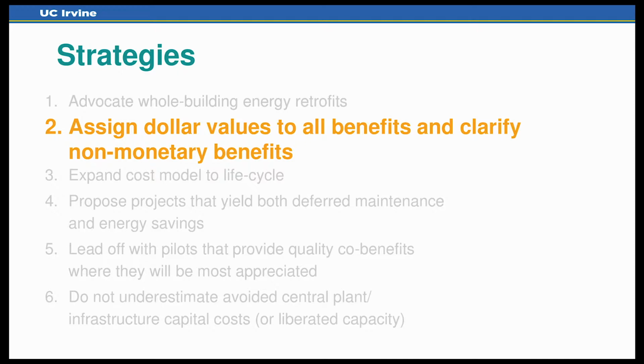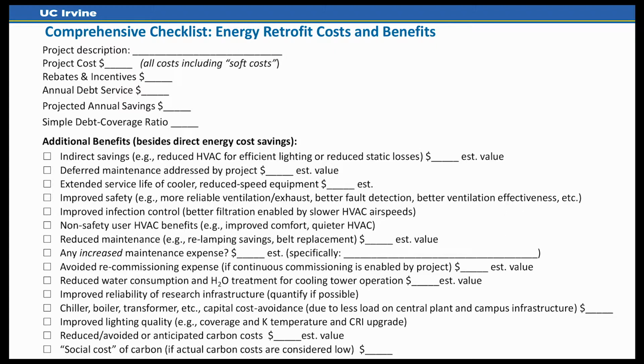So let's talk about examples. This is a typical energy retrofit project of about 10 years ago. So this isn't a whole building retrofit. This was actually before we started doing whole building retrofits. So this was a case of a building that had on the roof a whole bunch of individual exhaust fans, one for each fume hood actually. And they were belt driven. They were 1 and 2 horsepower motors. There was just like a whole farm of old 50-year-old fans up there.